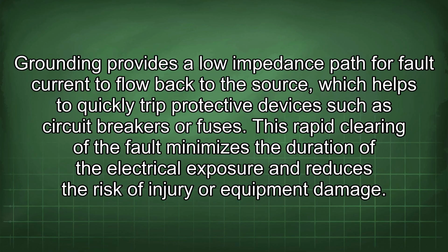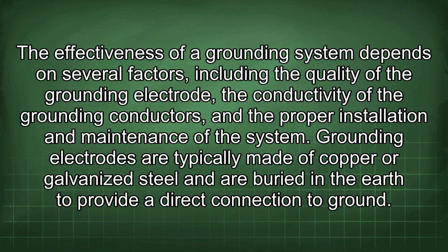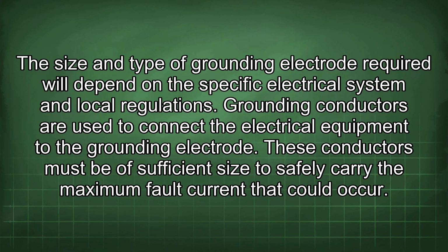This rapid clearing of the fault minimizes the duration of the electrical exposure and reduces the risk of injury or equipment damage. The effectiveness of a grounding system depends on several factors, including the quality of the grounding electrode, the conductivity of the grounding conductors, and the proper installation and maintenance of the system. Grounding electrodes are typically made of copper or galvanized steel and are buried in the earth to provide a direct connection to ground. The size and type of grounding electrode required will depend on the specific electrical system and local regulations. Grounding conductors are used to connect the electrical equipment to the grounding electrode.